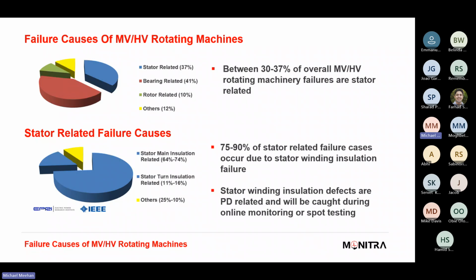So when we look at failure causes in the HV rotating machines, if we look at the top graph here, we can see that stator related and bearing related predominantly take up the majority of the failure modes. Rotors are less common. I'm pretty sure this is on the 3.3 kV and above machines. Yep, so this is all high voltage machines that we're talking about. And of those failure causes from that top bar chart, the stator related ones, there's a further breakdown from those stator related failures into what the failure mode is.